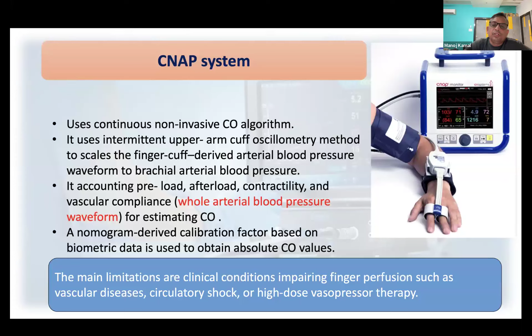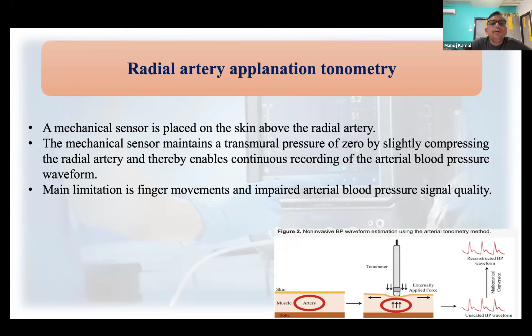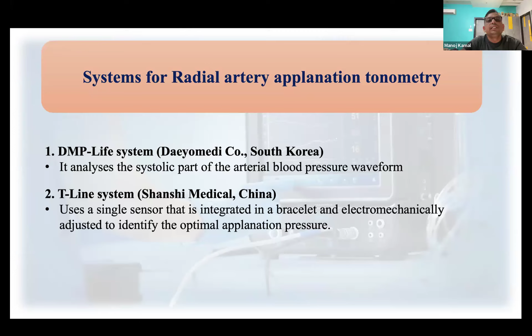such as vascular disease, circulatory shock, or a patient on high-dose vasopressor therapy. Radial artery applanation tonometry uses a mechanical sensor placed on the skin above the radial artery, and this mechanical sensor maintains a transmural pressure of 0 by slightly compressing the radial artery, thereby enabling continuous recording of the arterial blood pressure waveform. The main limitation is finger movement and impaired arterial blood pressure signal quality. The DMP Life system or T-Line system are the types of radial artery applanation tonometry.